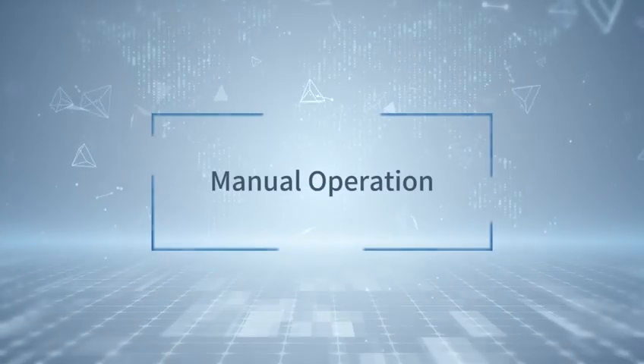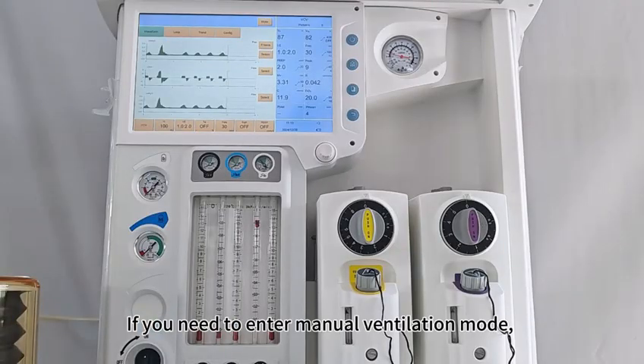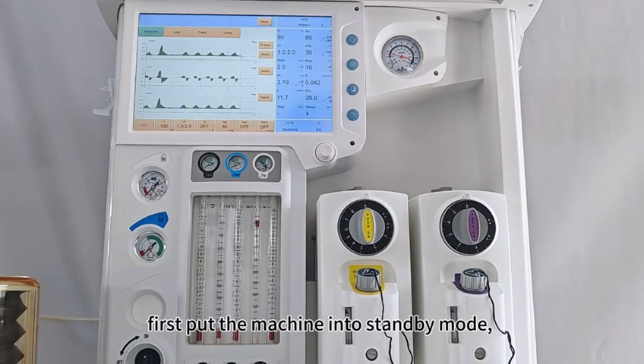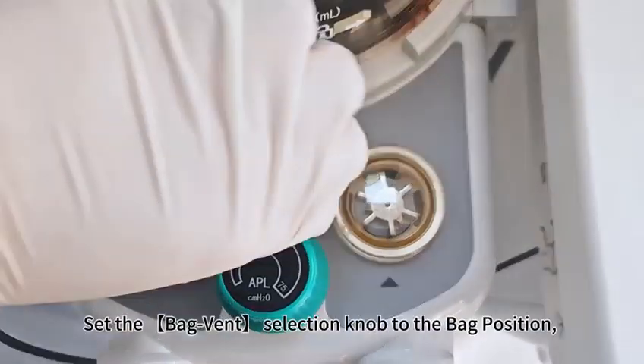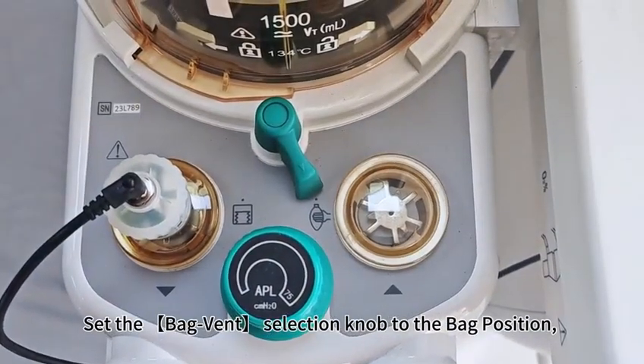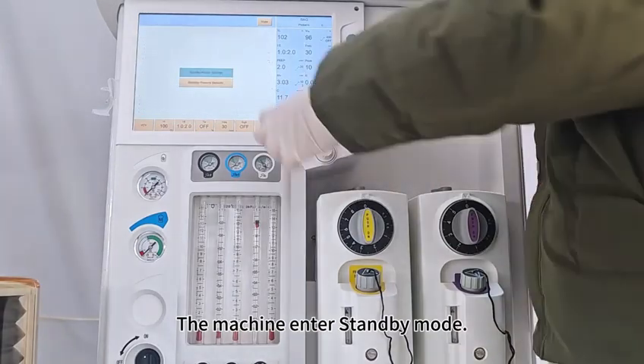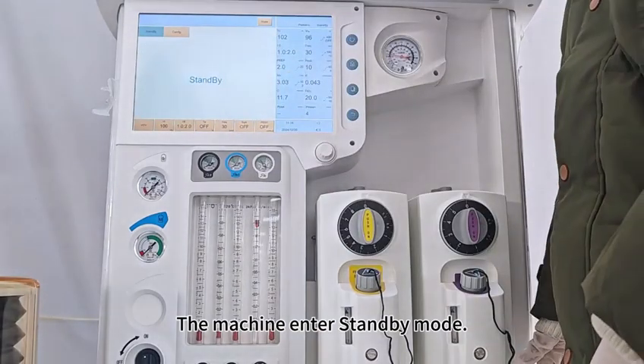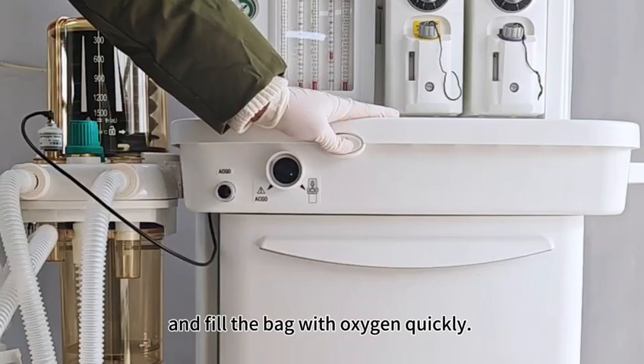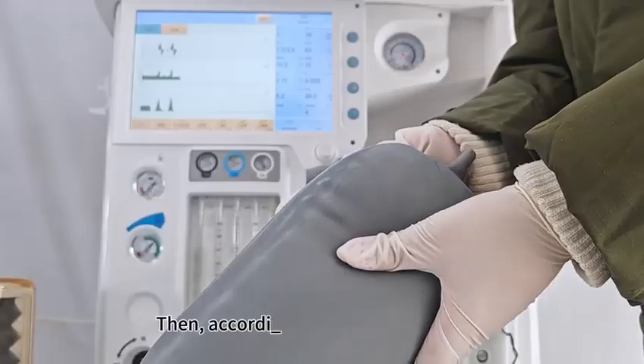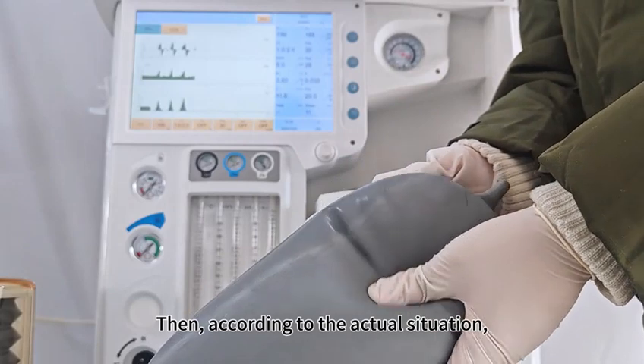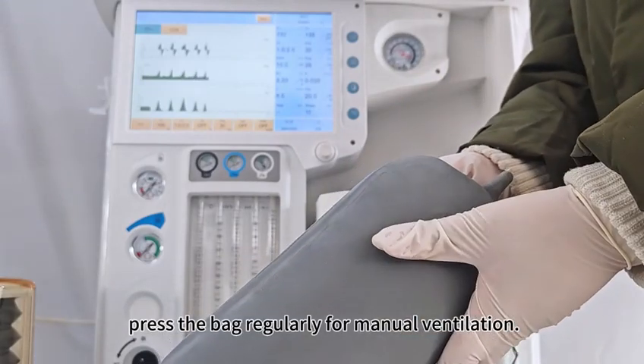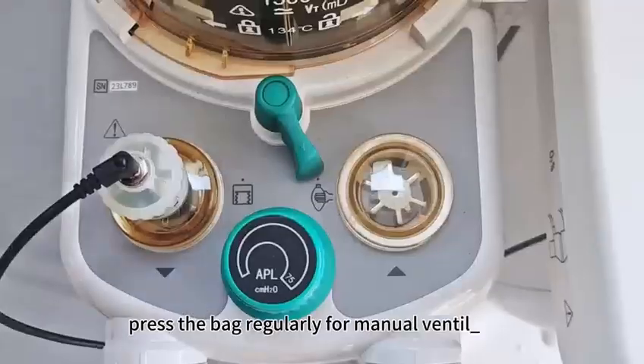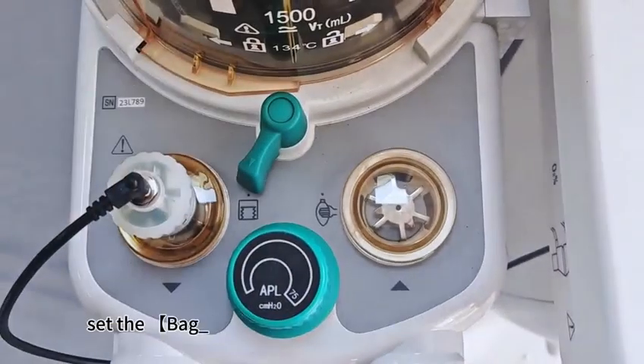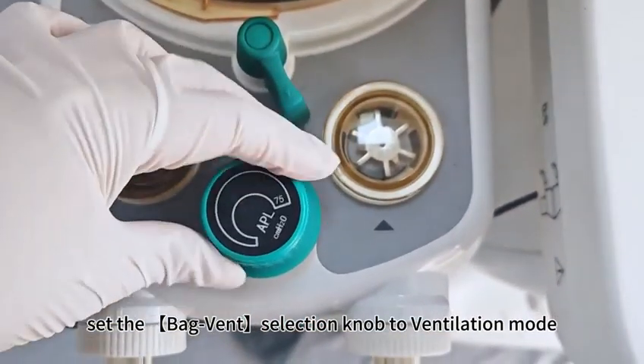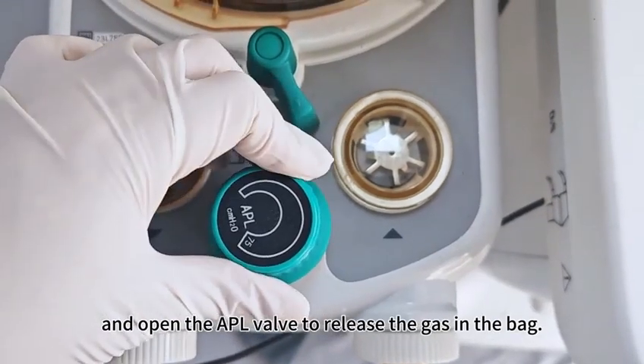Manual operation. If you need to enter manual ventilation mode, first put the machine into standby mode and set the bag vent selection knob to the bag position. The machine enters standby mode, and fill the bag with oxygen quickly. Then, according to the actual situation, press the bag regularly for manual ventilation. After manual ventilation is completed, set the bag vent selection knob to ventilation mode and open the APL valve to release the gas in the bag.